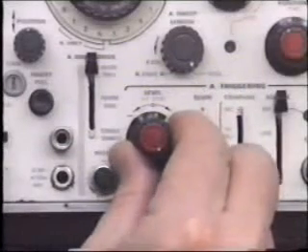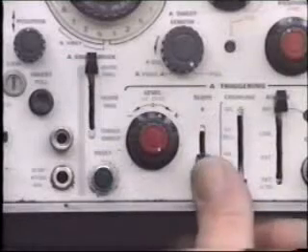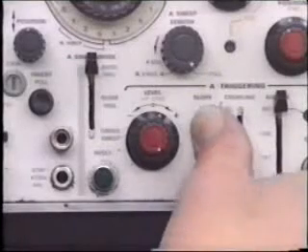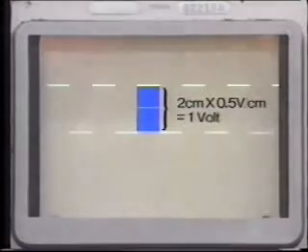At first, the waveform may be jittery or unstable. To improve this, we can adjust the trigger level and slope, positive or negative. You will also have to place the auto-norm trigger mode in the normal position now that we have an input signal. So, let's see what the display is telling us. In the vertical direction, we see 2 centimeters times 0.5 volts per centimeter, which equals 1 volt.